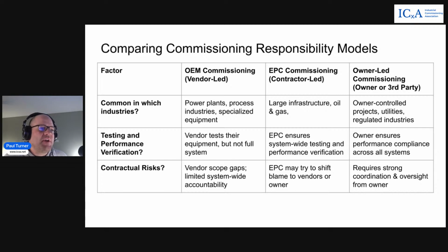Testing and performance verification: vendors test all the equipment, and also test the integration through dynamic commissioning if they're providing a system-wide solution. The EPC ensures system-wide testing and performance verification is completed on the owner's behalf. For owner-led commissioning, it's the owner's responsibility to perform static and dynamic commissioning, integration activities, and startup. There are various contract risks involved, as I've mentioned.